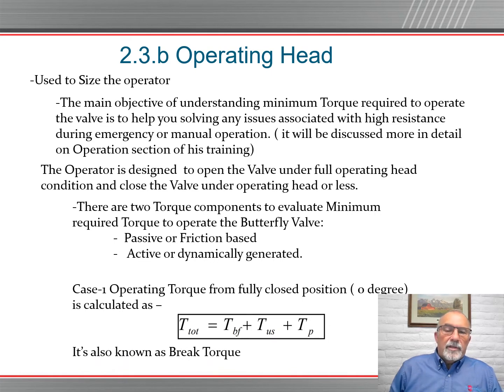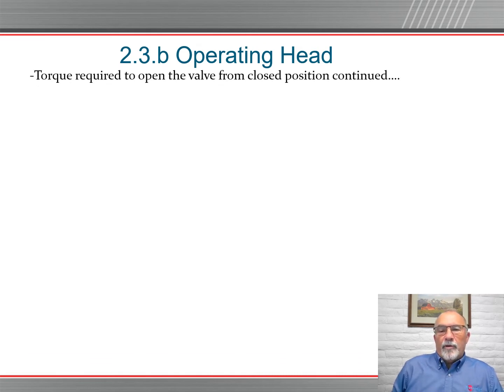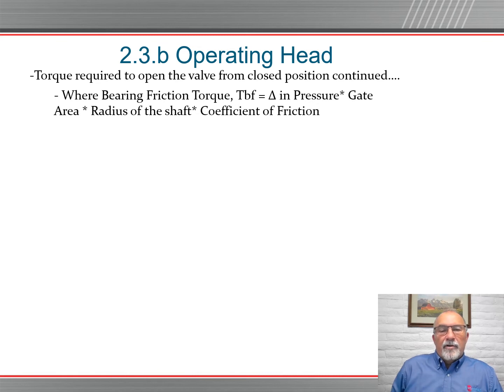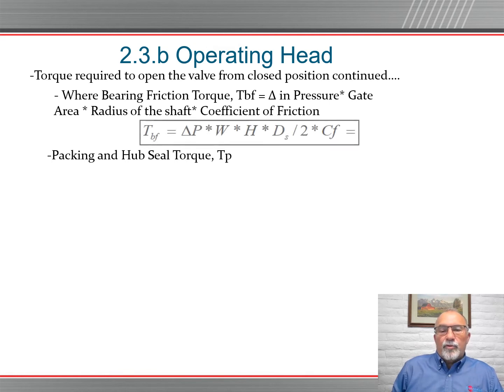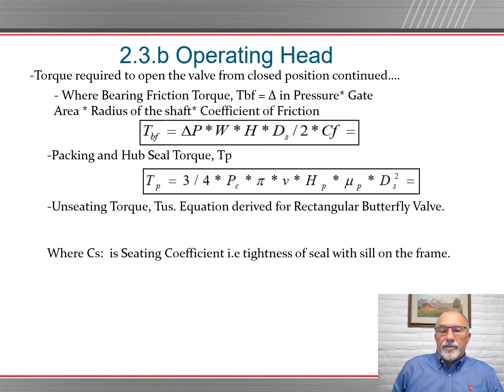There's the formula we use. This is probably a little more detailed than most of you want to know about, but the operating torque from fully closed position, 0 degrees, is calculated as, and you can follow through there, it has your total torque, and it breaks down the three different components of how we establish the torque. It's also known as the breakaway or the break torque. The operating head, the torque required to open the valve from closed position, this is continued from where we were at, where bearing friction torque, which is noted as TBF, then pressure on the gate area, the radius of the shaft, and the coefficient of friction, the drag of the rubber seats on your stainless steel seats, rubber seals on stainless steel. Packing and hub seal torque, there's lots of different factors to what increases the torque on these valves.